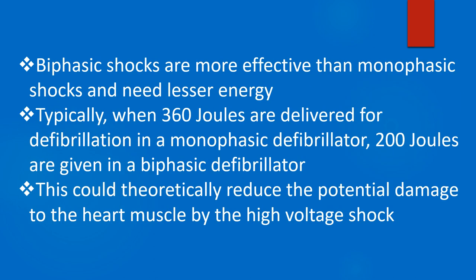Biphasic shocks are more effective than monophasic shocks and need lesser energy. Typically, when 360 joules are delivered for defibrillation in a monophasic defibrillator, only 200 joules are given in a biphasic defibrillator.